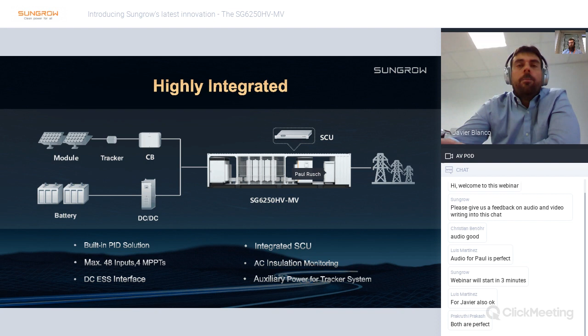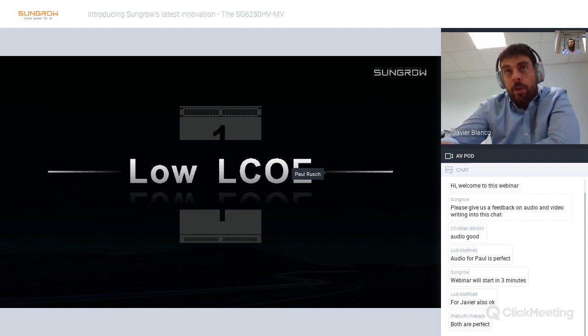One of the most important topics when designing a component for a PV plant is the minimization of LCOE. I'm going to show now how we contribute to reducing the LCOE in a utility scale PV plant. The first important parameter, of course, is the efficiency of the inverter. We achieve a maximum efficiency of 99%. This has been considered and fully optimized from the beginning with the right circuit design, algorithm concepts, proper selection of components, heat dissipation, everything counts here.